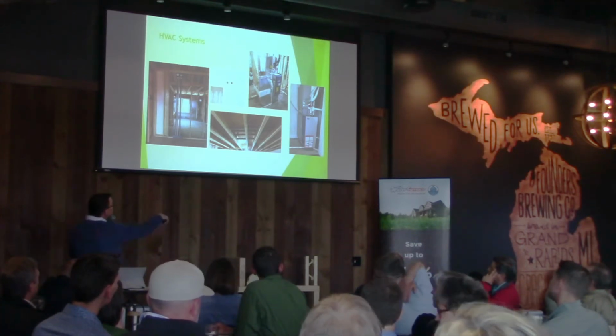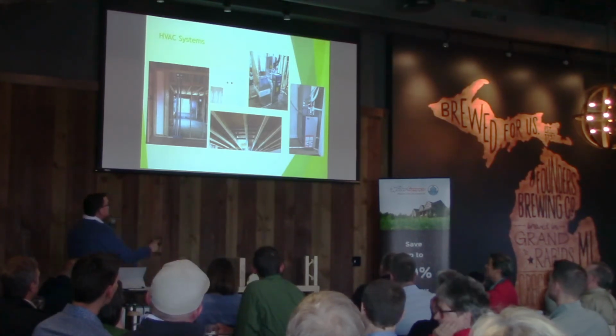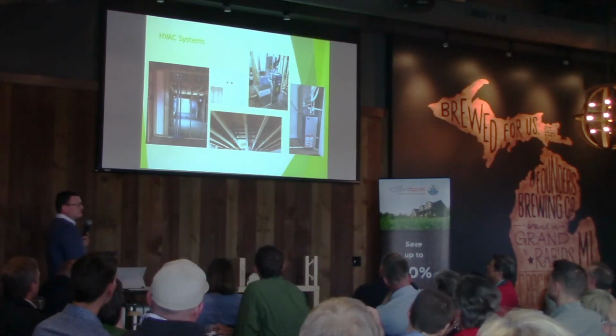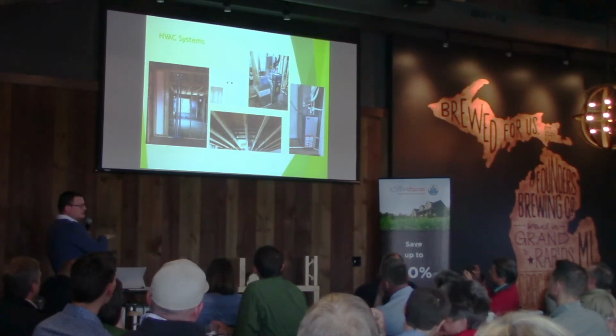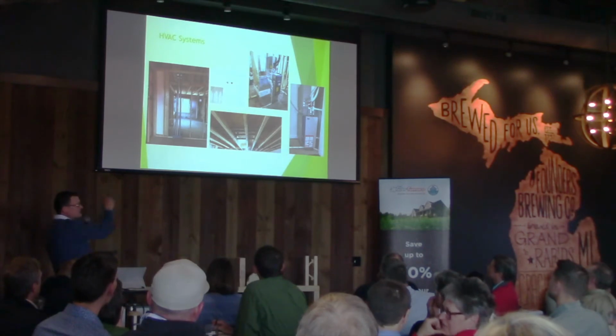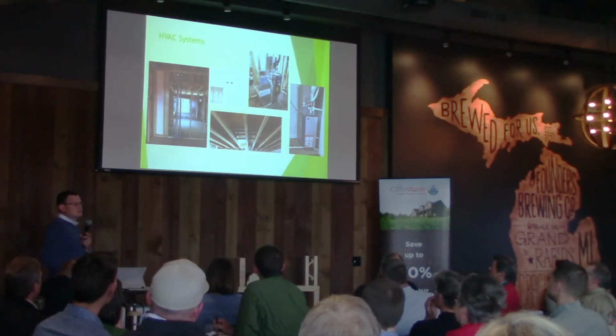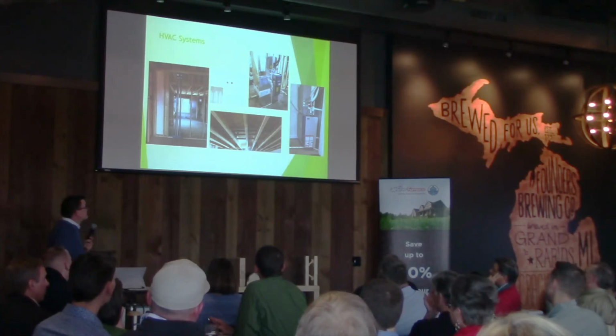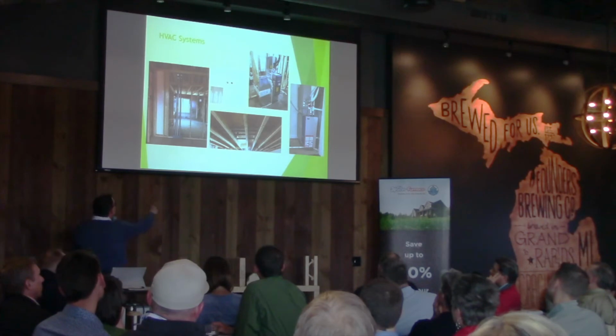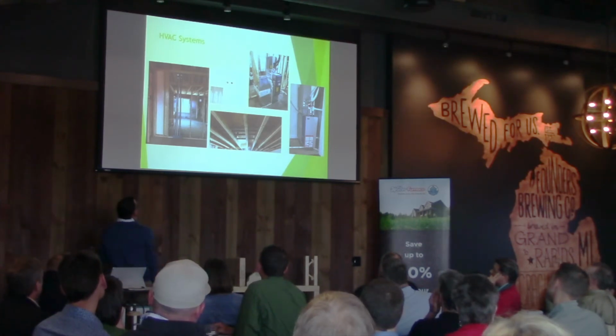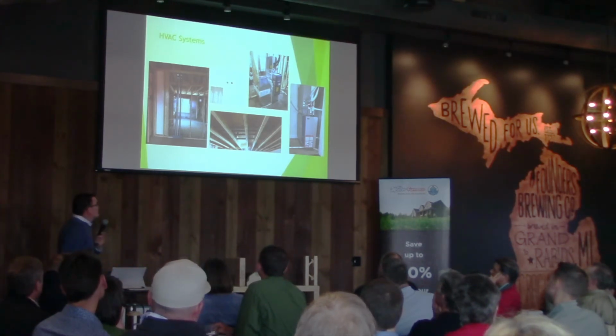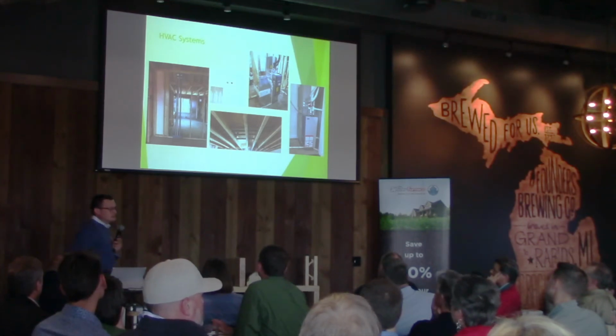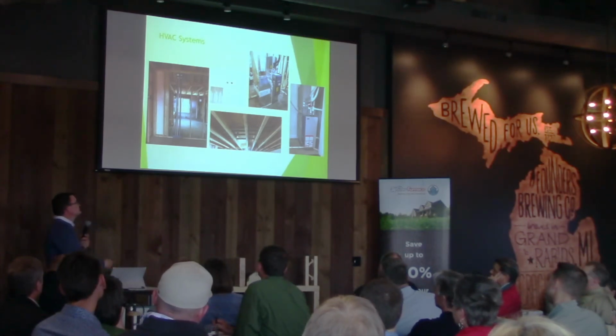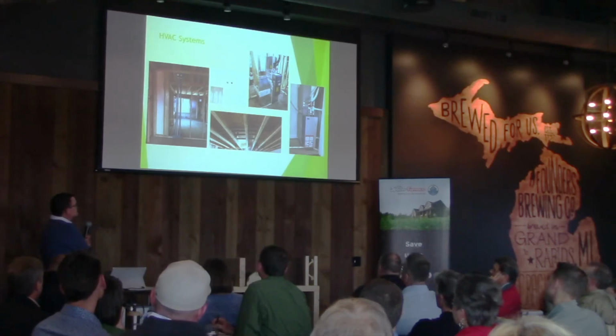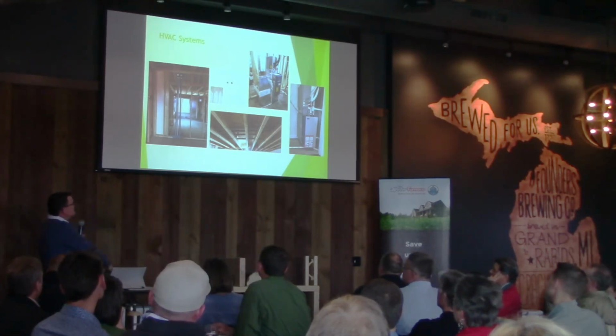That looks like a giant return air system, but that's just basically to handle the filter rack so that we could get that big MERV 11 filter in there. Once it gets above out of the picture, it goes to a 10 by 10 duct is all it's needed for that. So you don't have to run that huge duct work for return air. Inside your walls, all you have are these 2.5-inch flexible ducts. They are fire rated. That was usually the question we got from the inspectors over the first couple of years. They're fire rated. They're made out of fiberglass, actually, and they're really easy to drop through the walls.